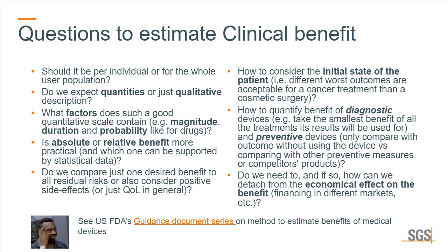So I mentioned previously clinical benefits. And this is a topic that is a little bit underdeveloped, I think, still in the medical device industry. There were some attempts already in the EN ISO 14971:2012 edition that try to talk about the benefit and how you should not just set up an arbitrary acceptance level for your risk, but the risk should be weighed against the benefit of the device. So if the device has higher benefit, then we are tolerating higher risk of using the device.